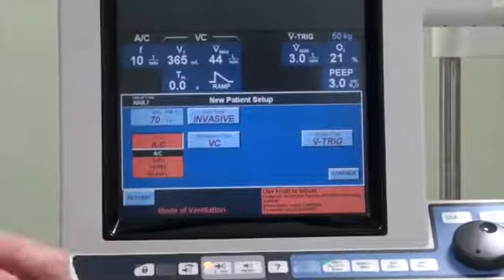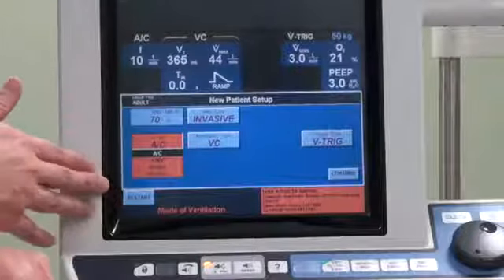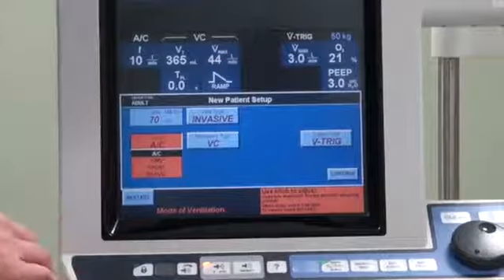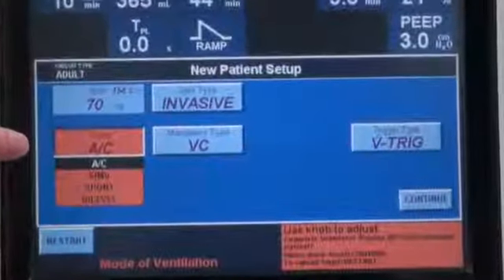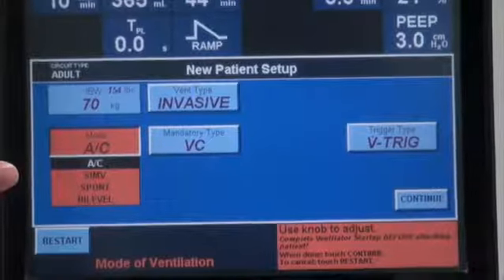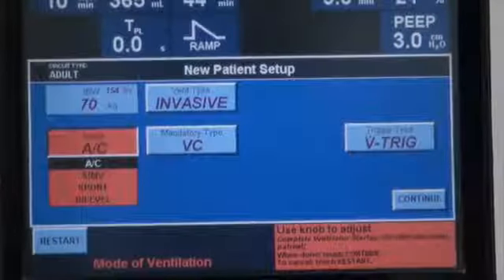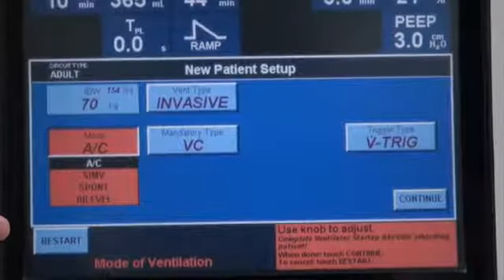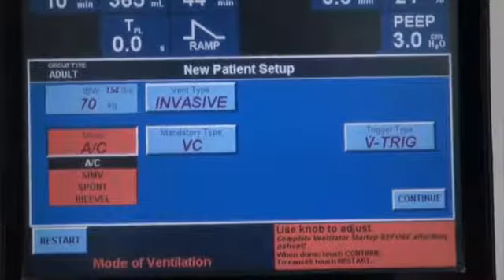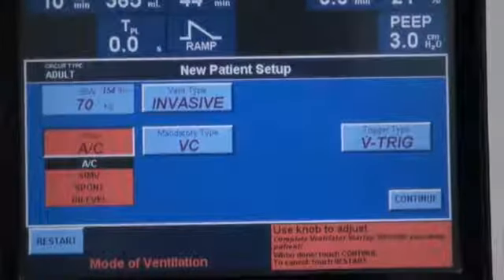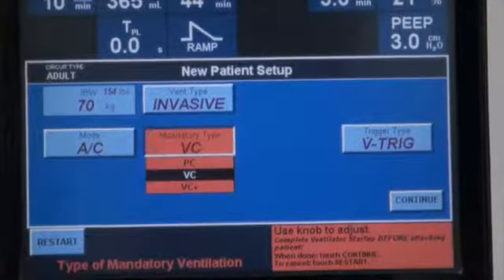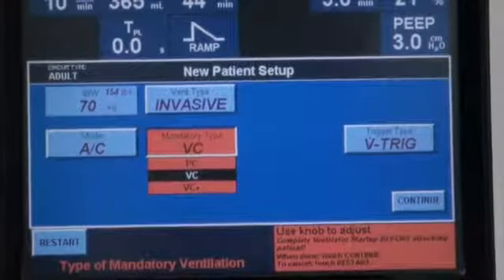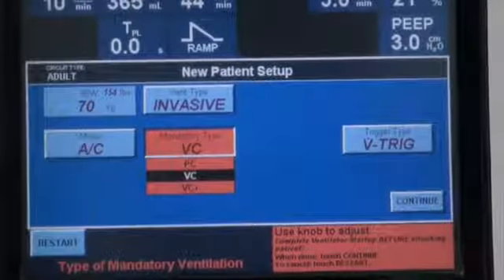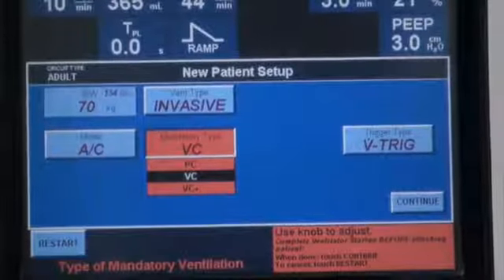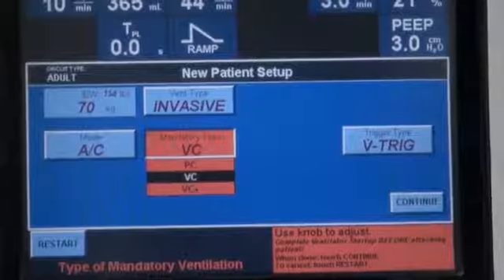Depending on the software that comes with the machine that you have, you will see that there are various modes that regulate how the ventilator delivers the breath. For this particular machine, there's assist control, synchronized intermittent mandatory ventilation, or SIMV. There's a spontaneous mode of ventilation, which is pressure support ventilation, and you can also do bi-level ventilation. For this demonstration today, we will be choosing the assist control. You can regulate the breath either using volume control or pressure control. There's an additional option of volume control plus, which is the equivalent of pressure regulated volume control in other ventilators. So for today's session, we'll focus on the assist control using the volume control mode.